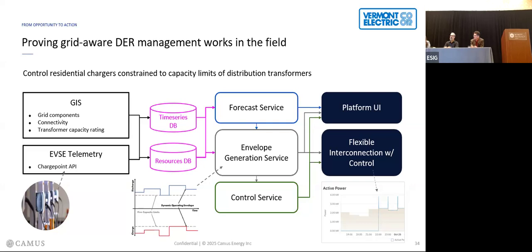We also aggregate information about transformer load in pseudo real time for every transformer on an ongoing basis, and use that to forecast the load for every transformer over a 2-day look ahead. We calculate a distribution envelope, basically a capacity envelope, for every EV located behind those, which gets communicated to the EV charger so it knows it needs to curtail at certain times. This uses a charge point program.